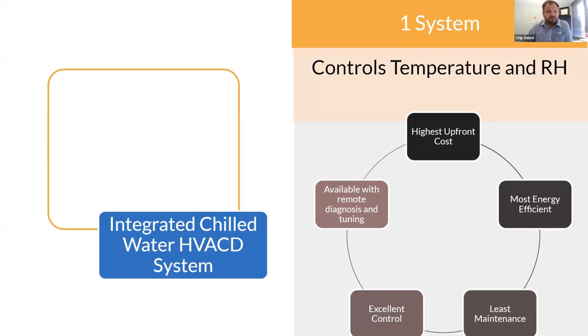Okay, and the last is the integrated chilled water HVAC system. These have the highest upfront cost, but they're the most energy efficient with the least amount of maintenance. You'll still have to maintain your chiller, which has a lot of the standard refrigeration components. We'll talk about that later. But the internal system, the air handlers, just deal with that low pressure water being piped through, extracting the energy needed to provide control.